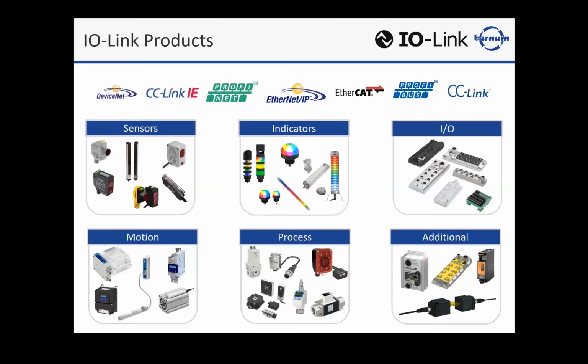Well, IO-Link has been very helpful in the process area too. So you're dealing with signals that would traditionally be analog. Now we can convert those signals away from analog, which a lot of times have a susceptibility to, say, electrical noise, for instance. And I've seen a lot of customers try to minimize that effect. So by switching it to an IO-Link device, we're able to get a digital value, and it's a much more safe and secure signal to get back to the PLC.